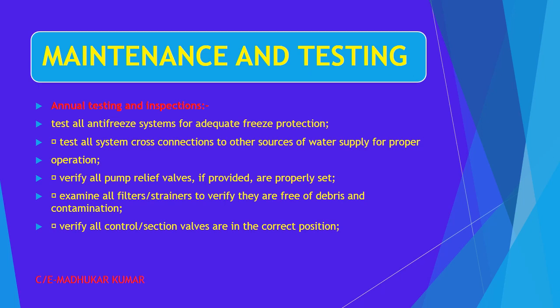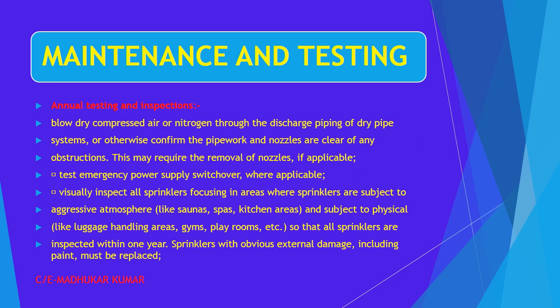Verify all pump relief valves, if provided, are properly set. Okay, and examine all filters and strainers to verify they are free of debris and contamination. Verify all control section valves are in correct position. Okay. Now continuation of annual testing. The dry compressed air, we have to blow it, and nitrogen, through the discharge piping or the dry pipe system, or otherwise confirm the pipe work and the nozzles are clear of obstructions.